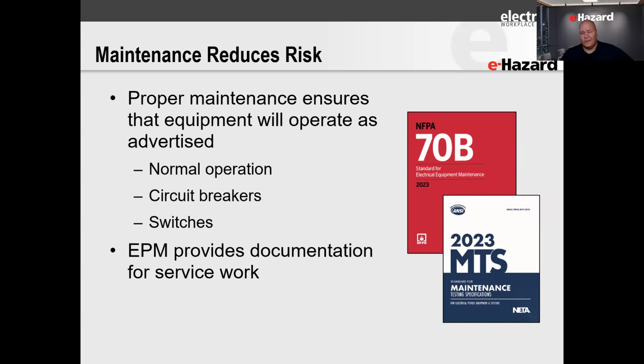All of those things are important from a maintenance standpoint, because if we base our arc flash study off a two cycle clearing time, and the actual clearing time is closer to 20, we have a much different amount of incident energy released in that arc flash than if we had been at 2 cycles.